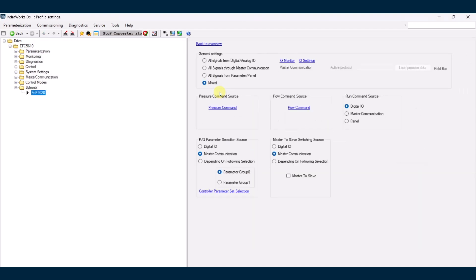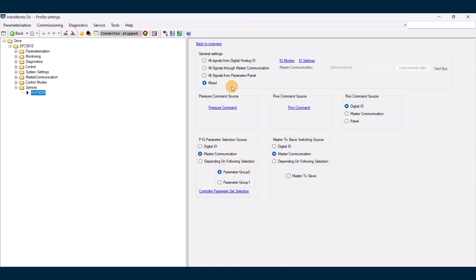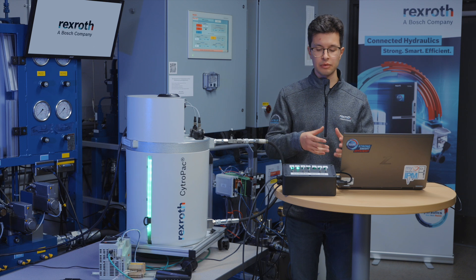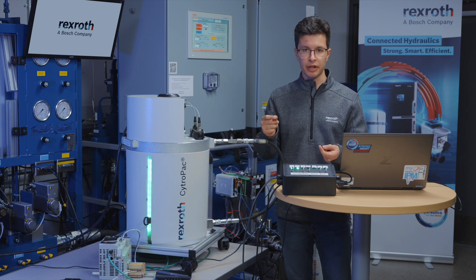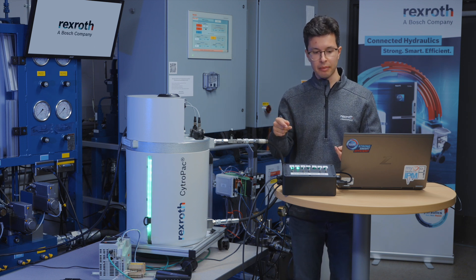Back to overview, then communication input. Next we're going to go to flow command source — we're also going to set this as a fixed value, and in this case we're only going to do 1000 RPM. Back to overview. Finally, for this demonstration, we're going to enable the CytroPac via 24-volt I/O. When I give it a 24-volt enable input, it's going to turn on the CytroPac to spin at a fixed flow up to the 20 bar pressure set point, then spin at the minimum RPM to maintain that pressure.